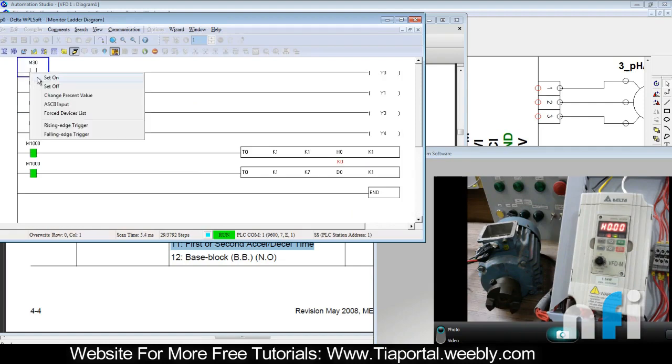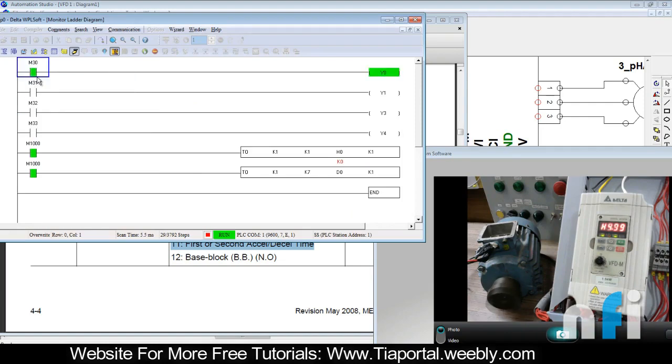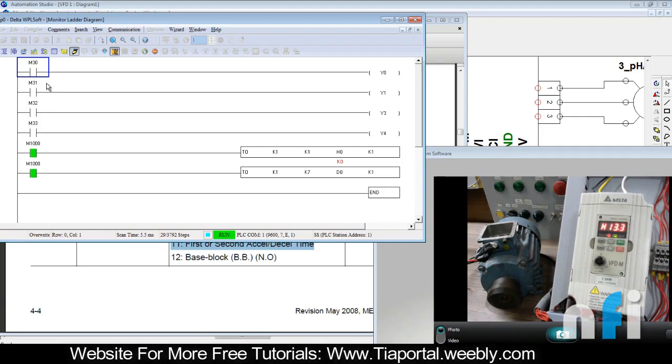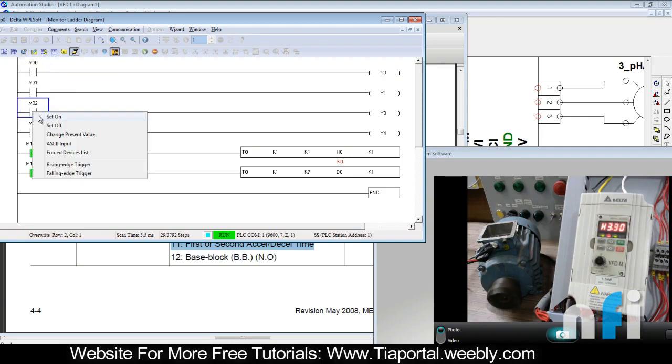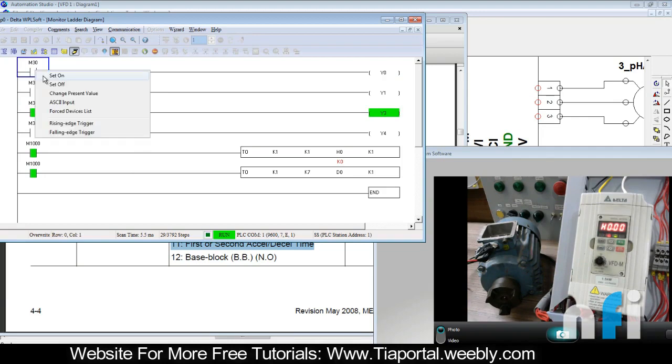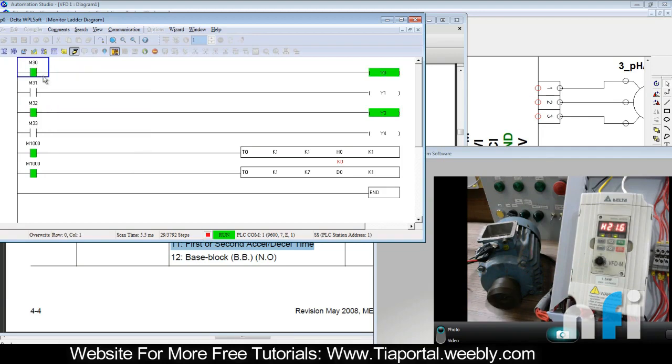Now I'll go back to PLC. If I run it as of now, it will increase slowly and reach the top command frequency of 21.6 Hz. If I turn it off, it will come back very smoothly. Now if I turn on Y3, the second acceleration has been selected. If I run M3, it will run all at once to 21.6 Hz.